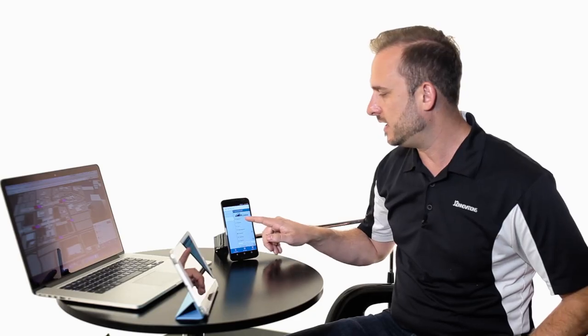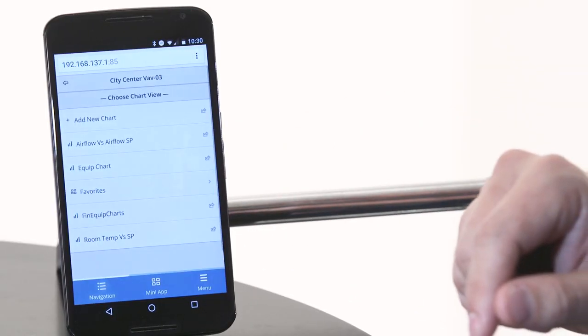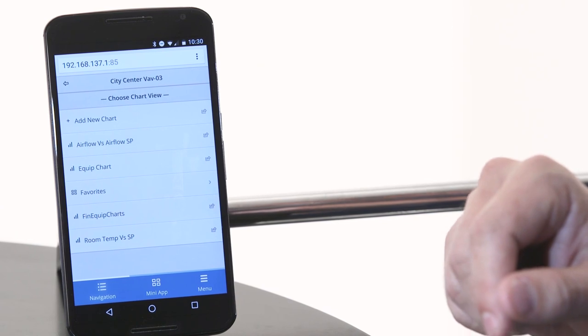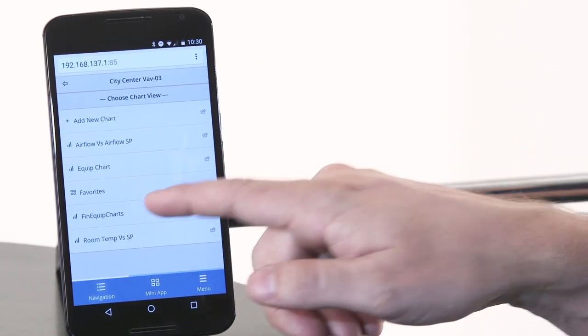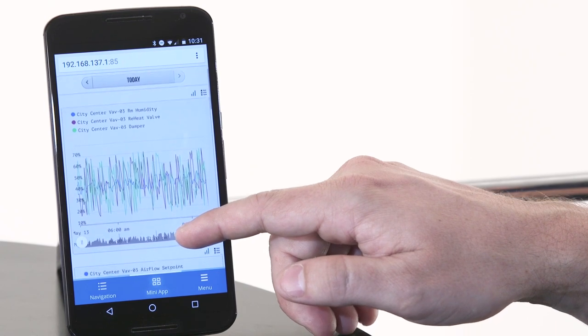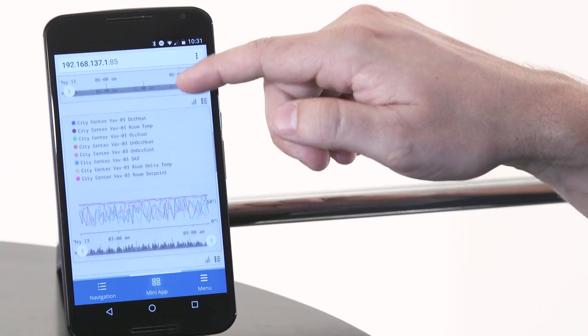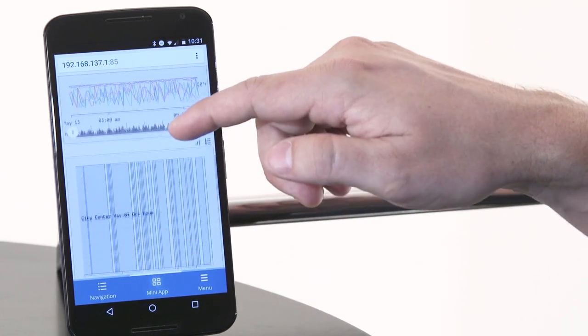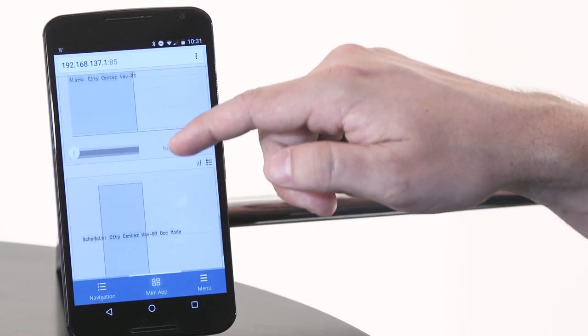Now let's go to the smart menu and find the historian app. Currently we're at VAV number three for City Center. In the historian app, you'll notice these are all the favorite histories that users created. Let's look at all the histories for this particular VAV — it shows all the points and lines them up on a chart. I'm on my phone right now and I'm scrolling up — it finds all the points, the boolean points, what the schedule's doing, and it shows all the alarms.